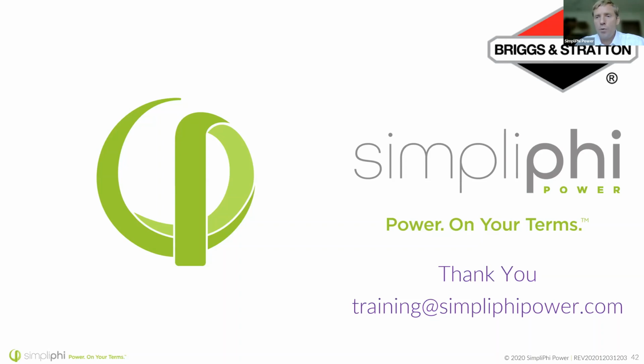What applications would you choose a 24-volt battery versus a 48-volt battery for? The essential difference is you'd choose a 24-volt battery based on other systems you need to draw from. If you're running systems that operate off DC, for instance, back in 2019 I did an installation in Ghana using a 24-volt battery bank. We were in a very remote off-grid location, and we chose 24 volts because we were operating 24-volt DC refrigeration systems for a remote ice-making facility for fishermen. So generally, the choice between 24-volt and 48-volt depends on what you're running off of it. If you're running DC equipment off your battery bank, you might choose 24 over 48. For most home backup systems, the standard now is really 48.